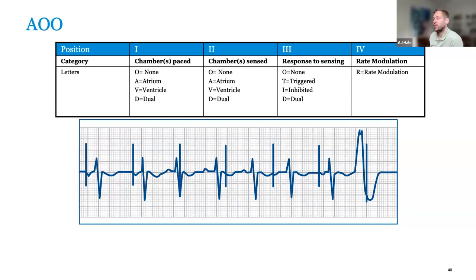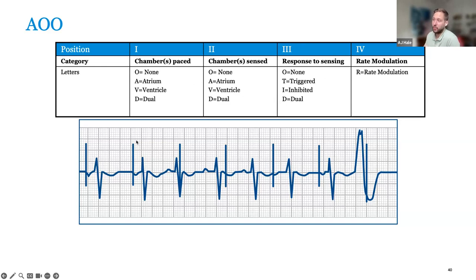AOO is very similar to VOO but pacing in the atrium instead. It paces in the atrium no matter what at the set base rate, senses nothing, and does nothing in response. You have an atrial pace, a negative P wave indicating captured atrial event, then it waits, times out, paces again. If an intrinsic atrial event occurs, the device is blind and paces anyway — that's functional non-capture. AOO can still be pro-rhythmic, but kicking off AFib is a lot less dangerous than kicking off V-fib. If the patient has good conduction, AOO is an option for surgery or if you have a lot of atrial over-sensing.